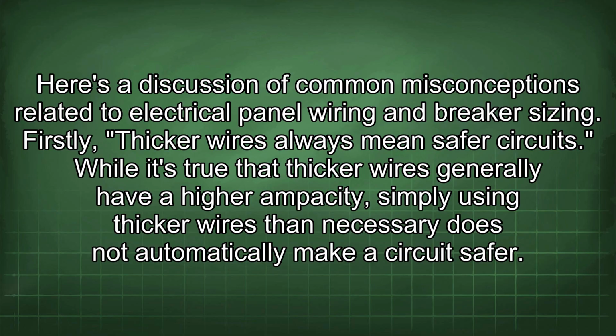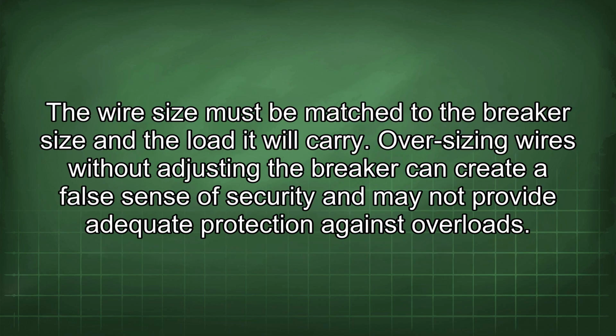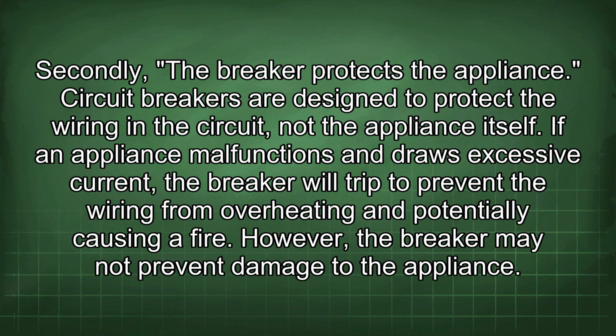Firstly, thicker wires always mean safer circuits. While it's true that thicker wires generally have a higher ampacity, simply using thicker wires than necessary does not automatically make a circuit safer. The wire size must be matched to the breaker size and the load it will carry. Oversizing wires without adjusting the breaker can create a false sense of security and may not provide adequate protection against overloads. Secondly, the breaker protects the appliance.